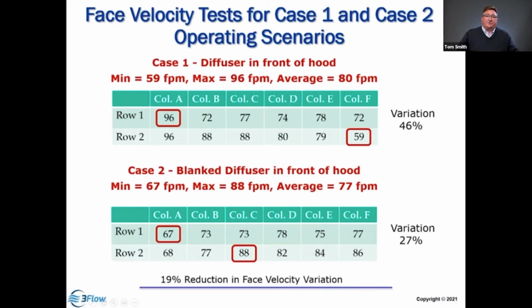Now, coming back to our situation where we're in case 1, the diffuser is loading the hood, versus case 2 where we're blanking off. In case 1, we can see that our variation went from 59 to 96, or a 46% variation, and that's unacceptable. And our velocity was 80 feet per minute, but when we blanked off, it went from 67 to 88, only a 27% variation. And it was a velocity of 77.